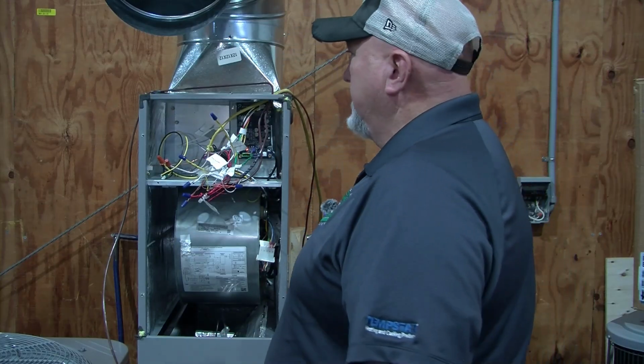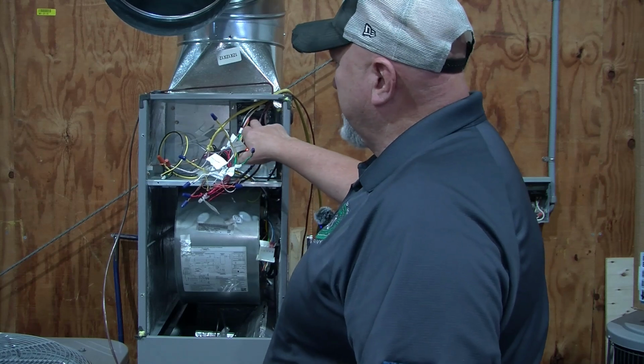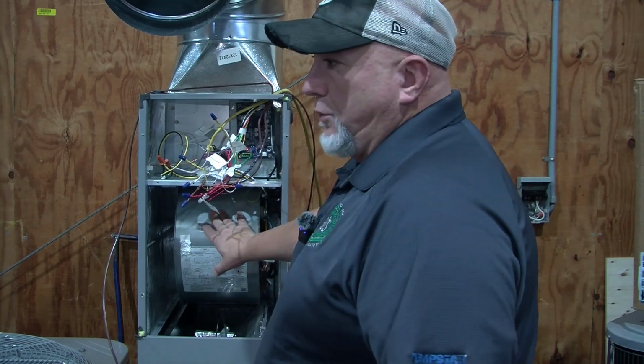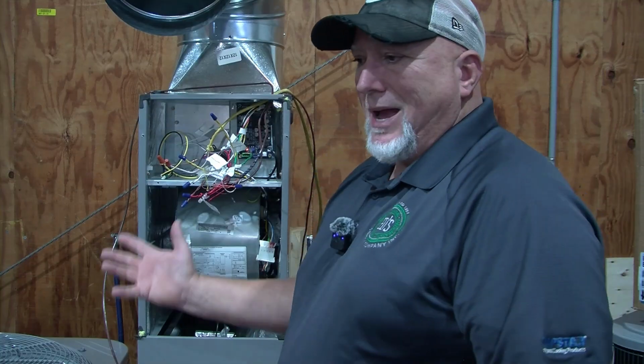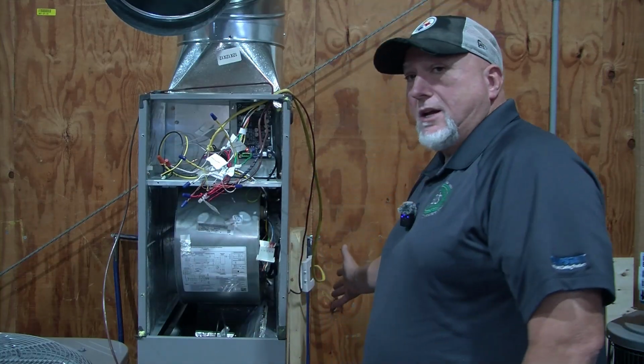Be patient with it, because all these, they've added in some timers. So this thing's going to run a few minutes. Then you'll be on your delay with your compressor delay, 3 to 5 minutes, sometimes 8, depending on what thermostat you have. So wait about that long, and the condenser unit should kick right back on, just like it should, because we're still getting a call for cool.